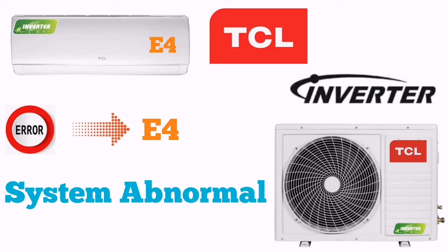And again, if you recharge the refrigerant and you are getting the same error, then you have to check the evaporator coil temperature sensor. If the resistance value is 5 kilo ohm at 25 degrees Celsius. If it's not showing the same resistance, then you have to change the evaporator coil temperature sensor.